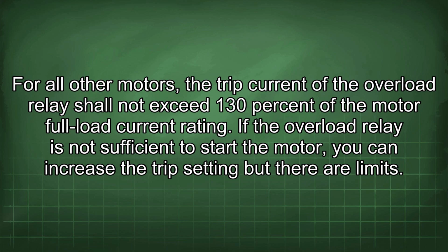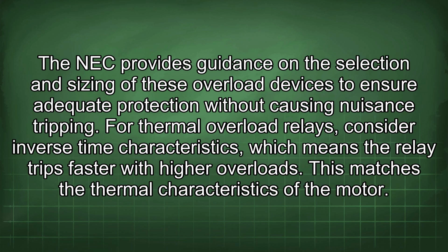If the overload relay is not sufficient to start the motor, you can increase the trip setting, but there are limits. The NEC provides guidance on the selection and sizing of these overload devices to ensure adequate protection without causing nuisance tripping. For thermal overload relays, consider inverse time characteristics, which means the relay trips faster with higher overloads. This matches the thermal characteristics of the motor.